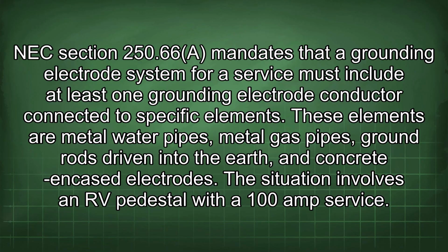NEC Section 250.66 mandates that a grounding electrode system for a service must include at least one grounding electrode conductor connected to specific elements. These elements are metal water pipes, metal gas pipes, ground rods driven into the earth, and concrete encased electrodes. The situation involves an RV pedestal with a 100 amp service.